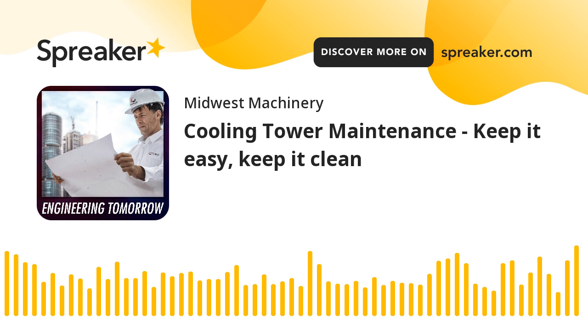With a fan being off pitch, is that what I've heard stories of, a fan blade flying off of the mount and piercing through the cooling tower? Would that have to do with the fan pitch, or is that the motor, or what would cause that? Wow. I've heard of that just kind of through the grapevine. Never really looked into it that much. I think there's got to be several things that go wrong. Like in any catastrophe, it's not just one thing that happened that was the cause of the problem. There are multiple things compounded that actually equaled that fan blade being thrown through a cooling tower. Okay. All right, so check the fan pitch.